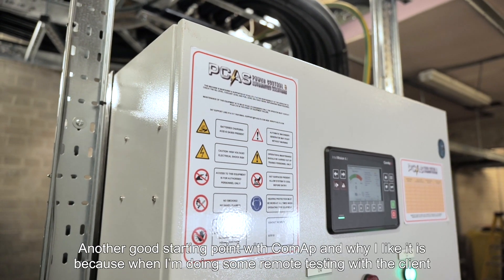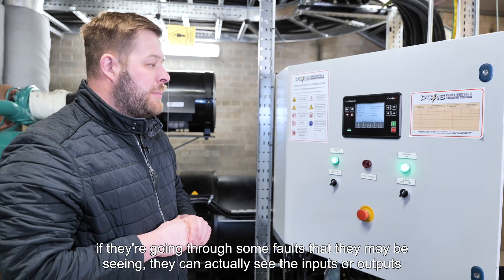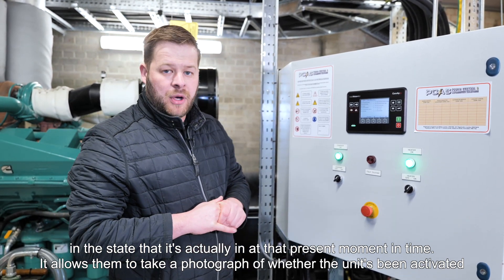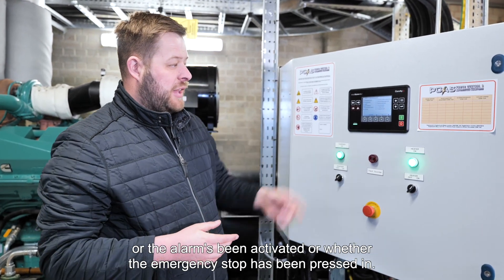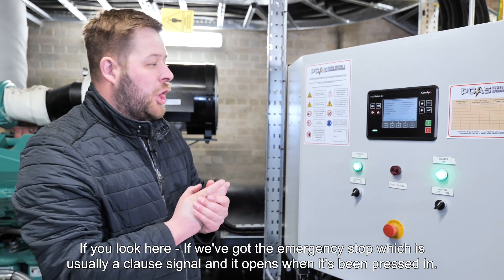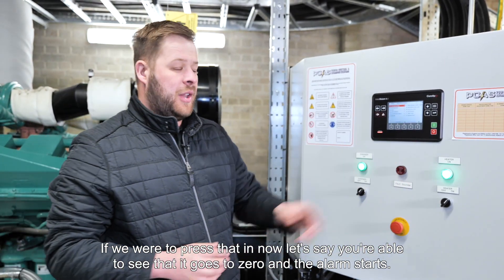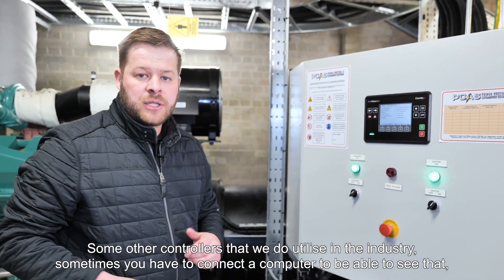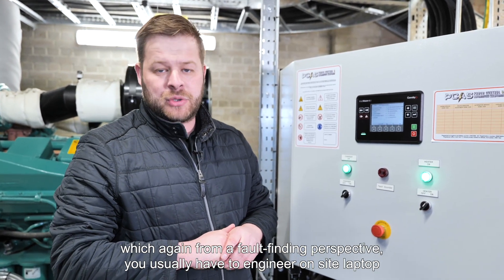Another good feature of ComAp is that when I'm doing remote testing with the client and they're going through some faults they may be seeing, they can actually see the inputs and outputs in the state they're actually in at that present moment in time. It allows them to take a photograph of whether the unit has been activated, or the alarm has been activated, or whether the emergency stop has been pressed in. If we look at the emergency stop — which is usually a closed signal and opens when pressed in — you're able to see it goes to zero and the alarm starts. With some other controllers used in the industry, you have to connect a computer to see that, which from a fault-finding perspective usually requires an engineer on site with a laptop and everything else required to complete that task.